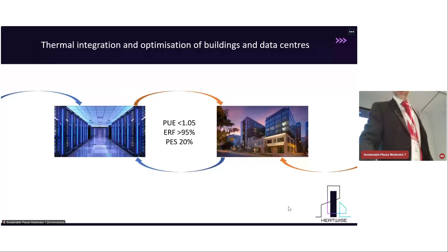We have three key KPIs here: PUE, ERF, and PES - power usage effectiveness, energy reuse factor, and primary energy saving. Why are they important? This is how we measure ourselves against others. PUE is the best, or most commonly used, KPI in the data center.